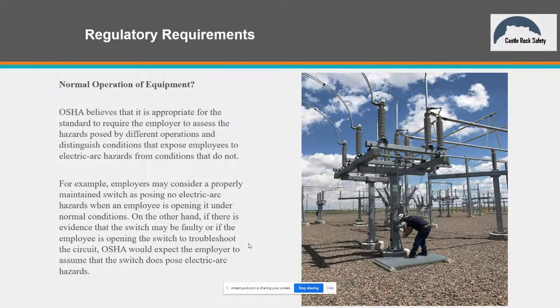I'll go do audits, and I've got clients that I'll go out and see, and you'll see somebody opening a switch. This is a fairly low profile switch, and I'll see this guy standing there, and they'll put him in a 40-calorie suit, down in South Texas in a substation, where the heat index is 118 degrees. That's the kind of thing I'm seeing on the supply side. There is so much confusion about what that guy is required to wear.